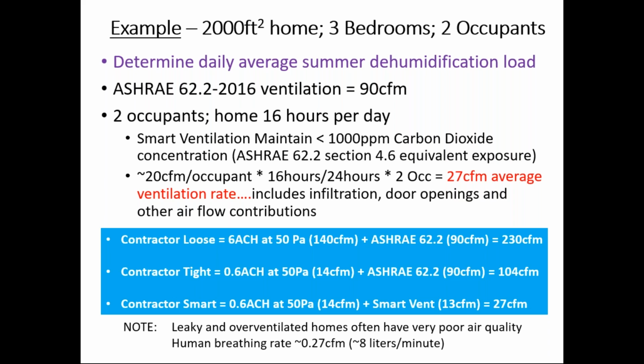Now, Contractor Smart, with this type of occupancy, builds a smart ventilated home, which is an automatically ventilated home that monitors air quality, VOCs and CO2, and then brings in fresh air as you need it. When it's windy out, when the doors are open and closed a lot, the smart ventilation system senses that and doesn't need to bring in as much air. And when it's not so windy, or there are a lot of occupants, it can increase or decrease. But on average for this home, we assume that it needs about 27 CFM to keep air quality controlled.